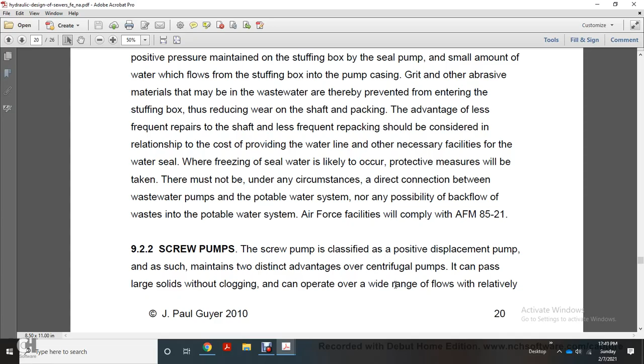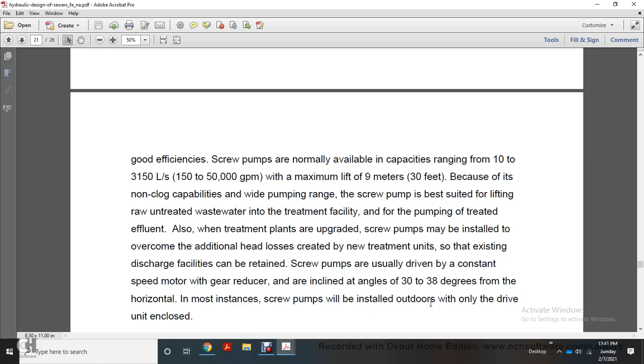Because of the non-clog capability and wide pump range, screw pumps are best suited for lifting raw untreated wastewater into the treatment facility and pumping treated effluent. With treatment plant upgrades, a screw pump may be installed to overcome additional head loss, so with the new treatment units, existing discharge facilities can be retained. Screw pumps are usually driven by a constant speed motor with gear reducer and inclined at angles of 30 to 38 degrees from the horizontal. In most instances, screw pumps will be installed outdoors, with only the drive units enclosed.